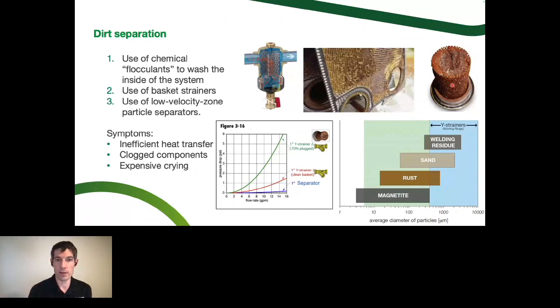The problem with a Y strainer is anything smaller than the mesh is just going to keep getting pushed through it. So you're going to catch big stuff with a Y strainer: welding slag, big pieces of sand, big chunks of rust, a welding glove. We got back an 8-inch separator one time. They said it wasn't flowing very well. We opened it up and there was just a leather welding glove inside of it. It's going to catch that stuff. But little magnetite and pieces of rust and pieces of sand are just going to go right through that mesh all the time. You can get a smaller mesh, but it's just going to plug faster.